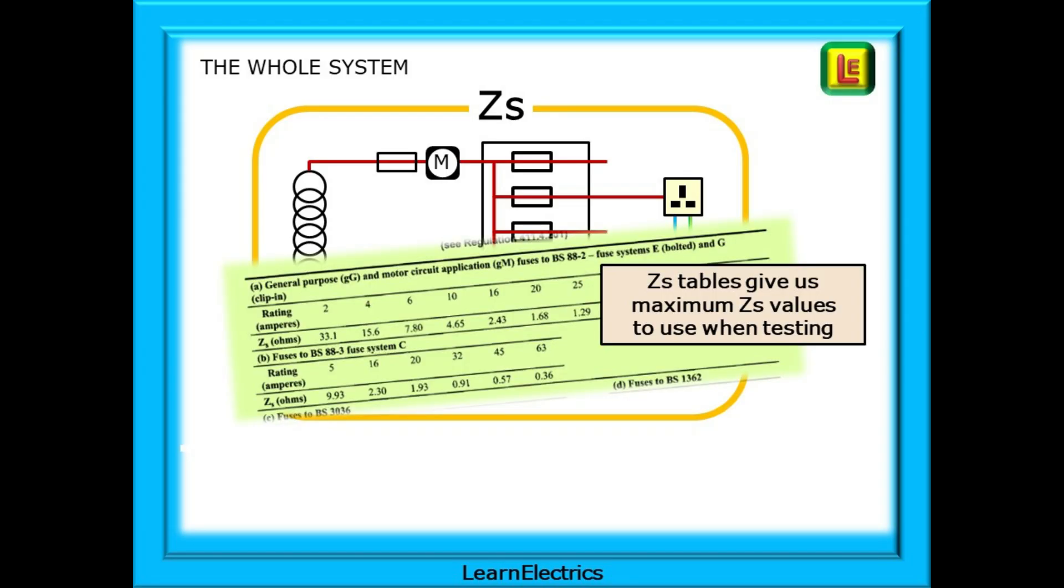To start with, why do we want to know ZS, the impedance of the whole system from every point of use? So that we can compare the test results to data shown in the wiring regulations and the on-site guide. If the impedance is less than the figures supplied for each fuse or breaker size, then we are assured that the safety devices, the fuses and breakers, will operate as required if a fault occurs.